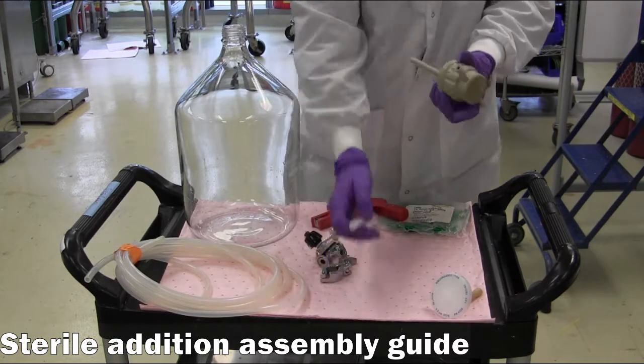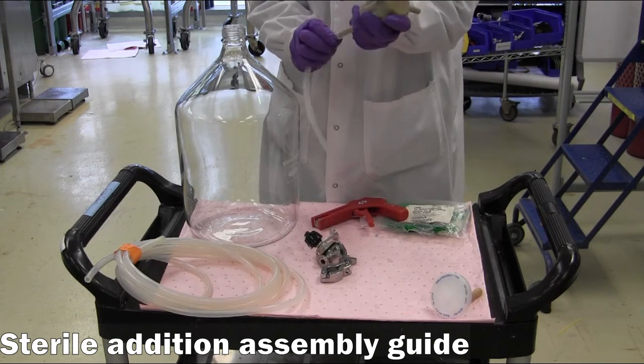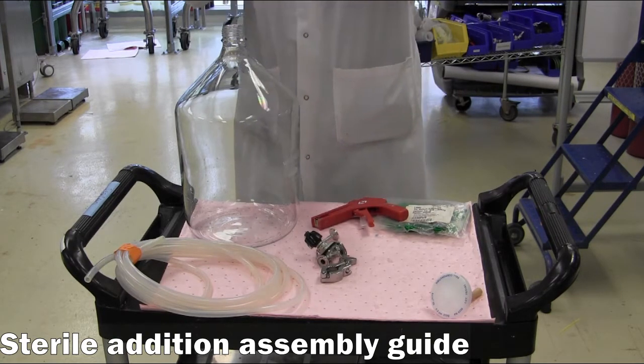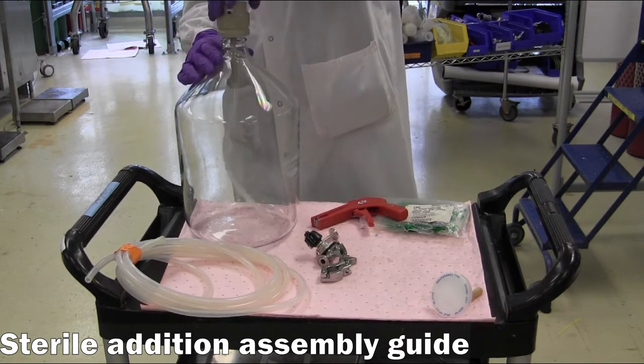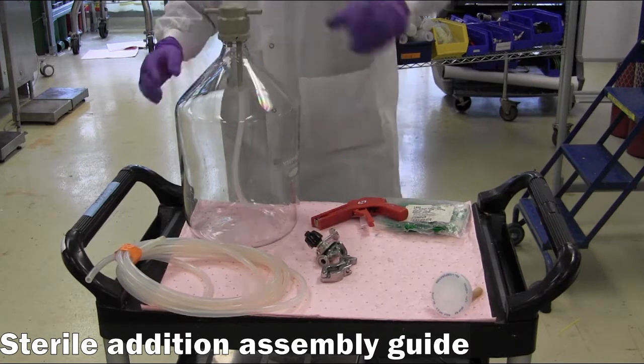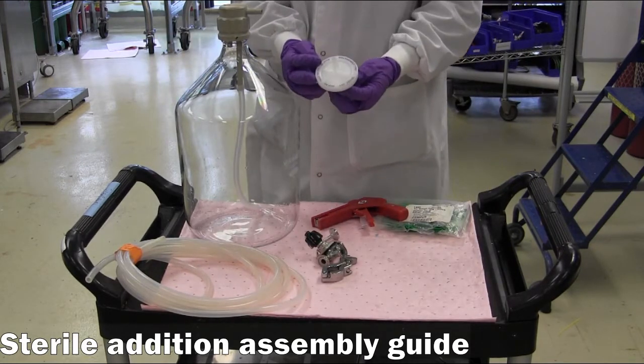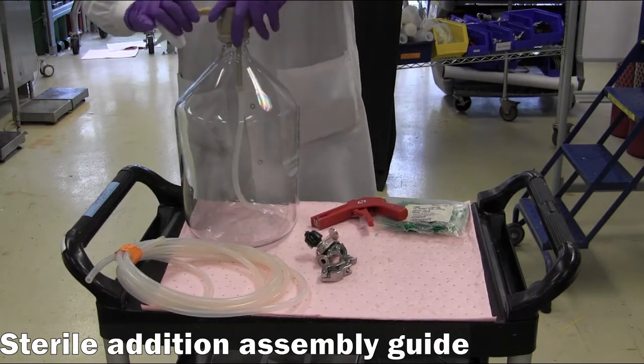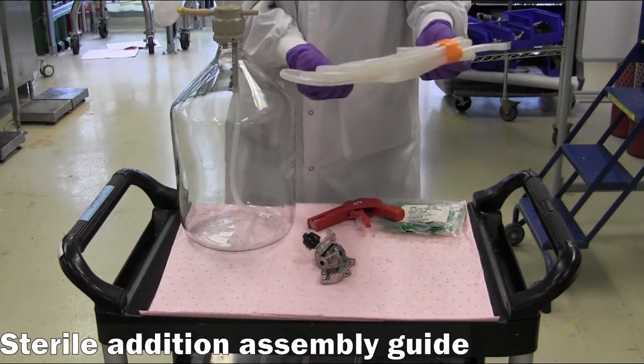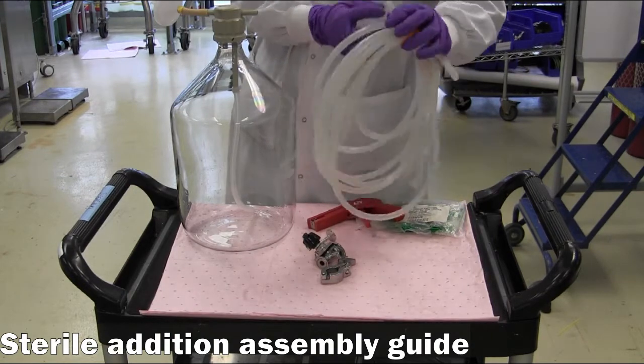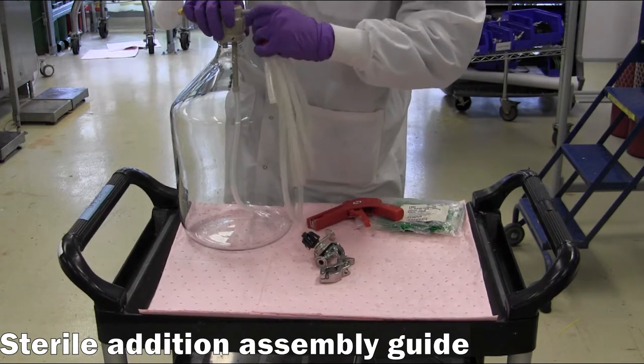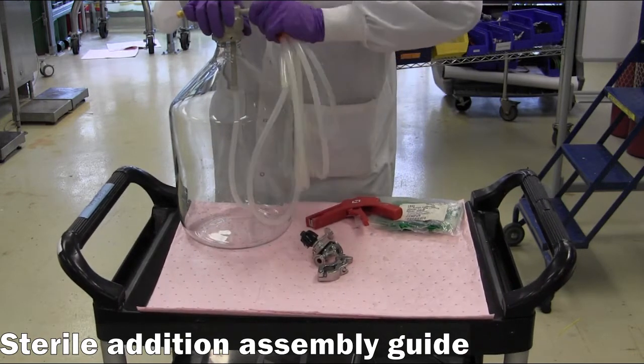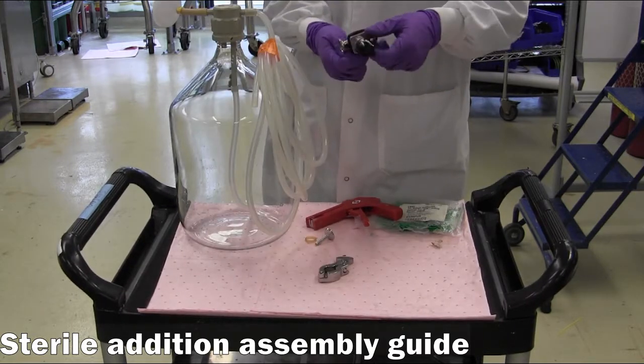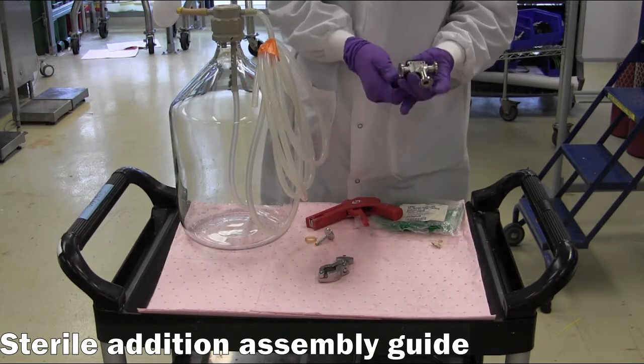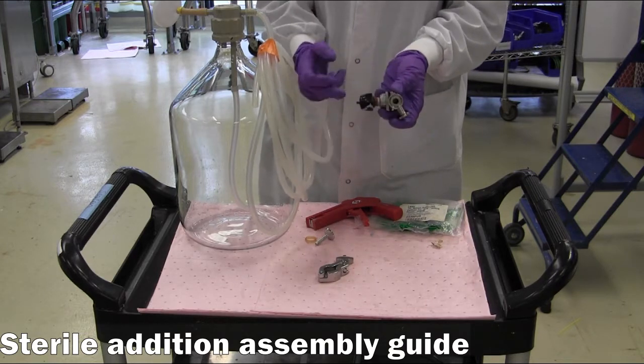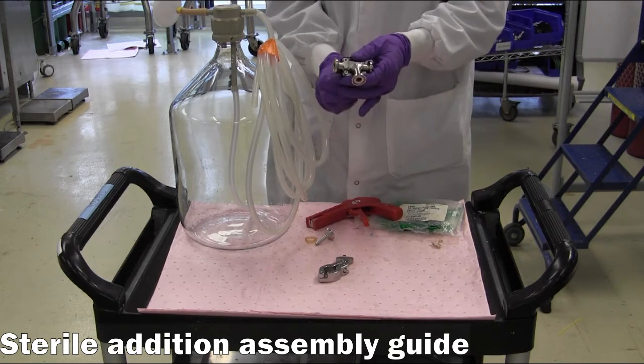Attach a dip tube to the bottom port of the additive bottle top or cap. Next, attach a 0.2 micron filter to the non-dip tube outlet and the transfer line to the dip tube outlet. A hand valve goes on the other side of the transfer line. Make sure this hand valve is closed. A red band marks the position of the hand valve. The red tape is visible when the valve is open.